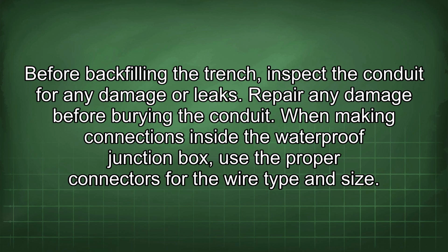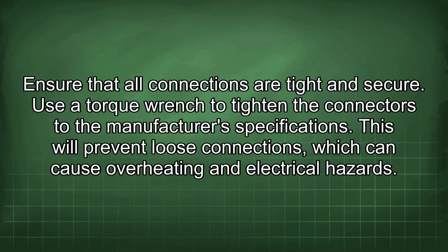When making connections inside the waterproof junction box, use the proper connectors for the wire type and size. Ensure that all connections are tight and secure. Use a torque wrench to tighten the connectors to the manufacturer's specifications. This will prevent loose connections, which can cause overheating and electrical hazards.